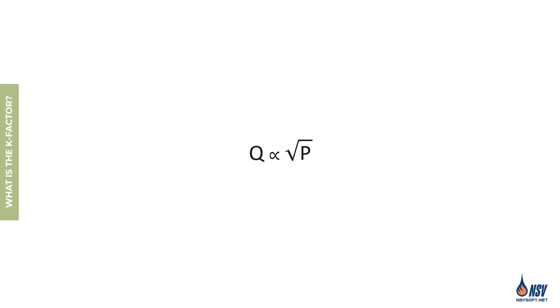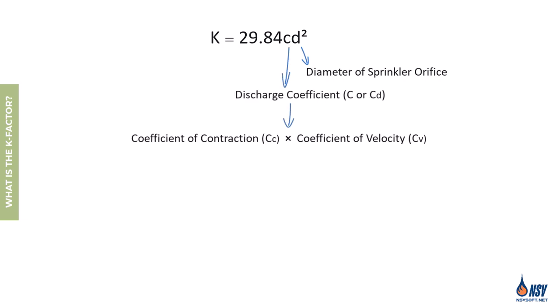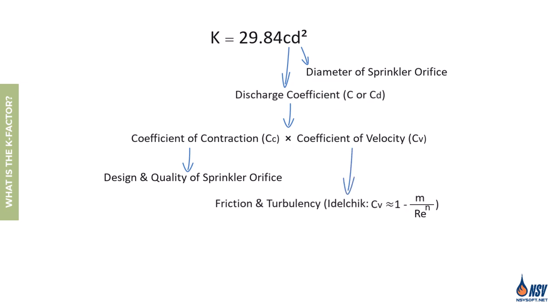The discharge flow rate of a sprinkler is proportional to the square root of its operating pressure. The proportionality constant that converts this relationship into a usable equation is called the K factor. The K factor can be obtained using the formula: K = 29.84 × C × d², where d is the sprinkler orifice diameter in inches and C is the discharge coefficient — the product of the coefficient of contraction and the coefficient of velocity. The coefficient of contraction varies with the design and manufacturing quality of the sprinkler orifice.